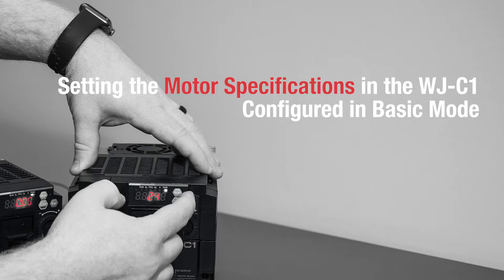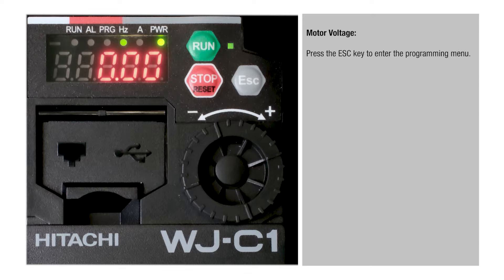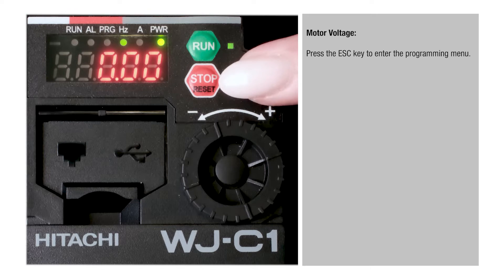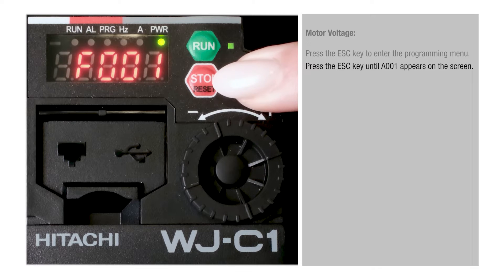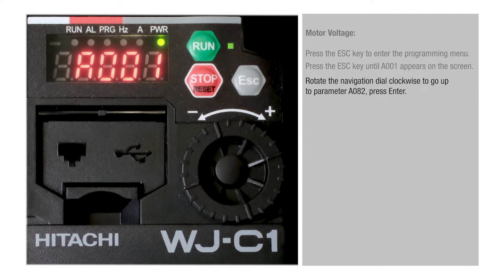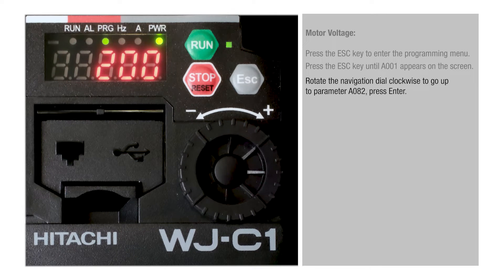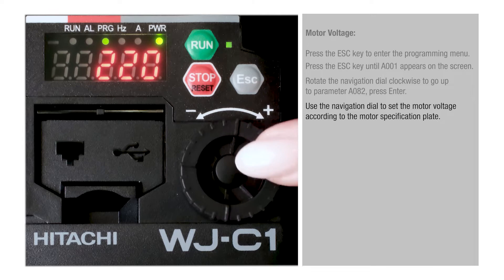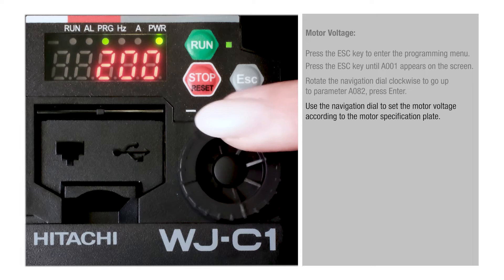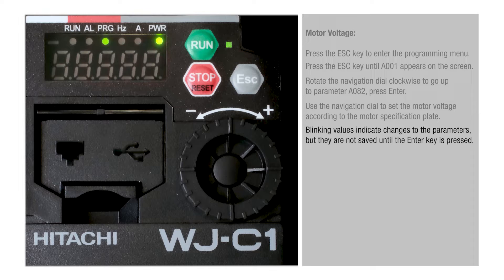Setting the motor specifications in the WJC1 configured in basic mode. Motor voltage: press the Esc key to enter the programming menu. Press the Esc key until A001 appears on the screen. Rotate the navigation dial clockwise to go up to parameter A082, then press Enter. Use the navigation dial to set the motor voltage according to the motor specification plate. Blinking values indicate changes to the parameters, but they are not saved until the Enter key is pressed.